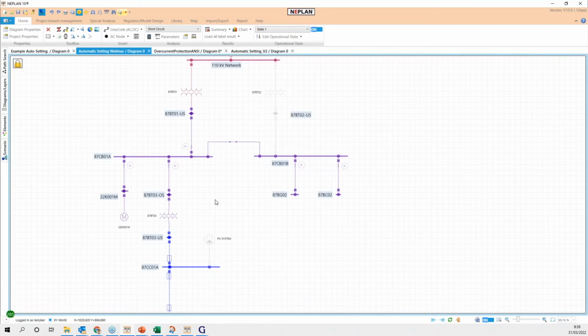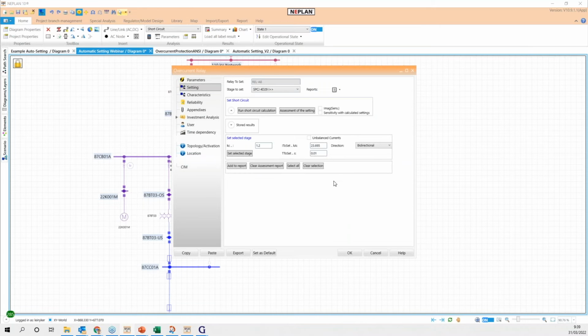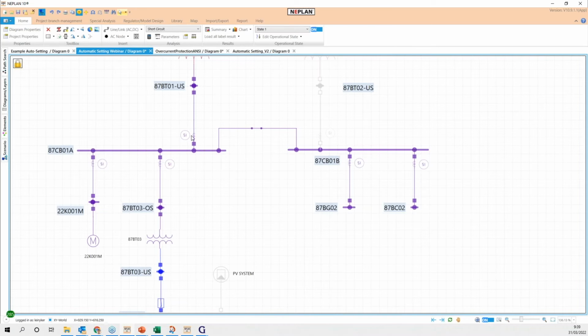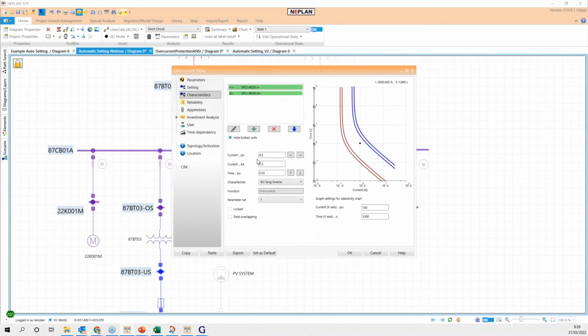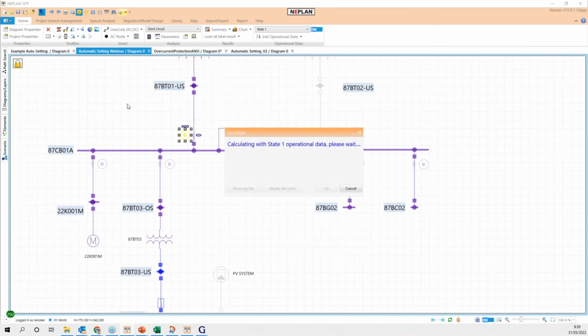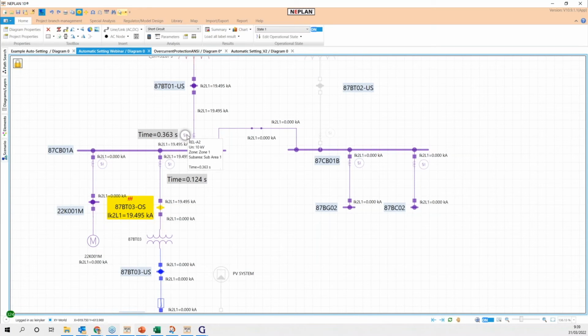So protection assessment of NEPLAN allowed to get the validation of the existing settings of the network, but also it allowed to check using the automatic setting of NEPLAN if we can change that automatically or not. For sure, we can change that because for this operation, NEPLAN allows to define a new setting group. For example, I can change the setting group of this relay because once I run the simulation, we can see that we have increased the tripping time here because we moved the setting. And now the difference between both protections is bigger than 200 milliseconds and doesn't exceed the 400 milliseconds.